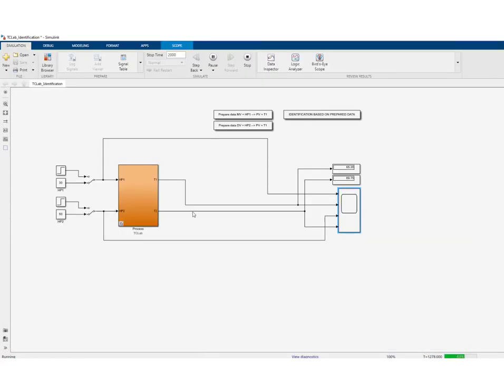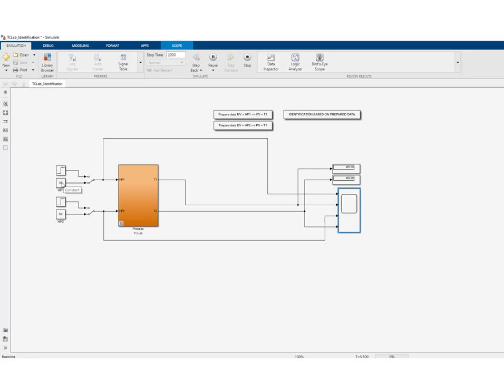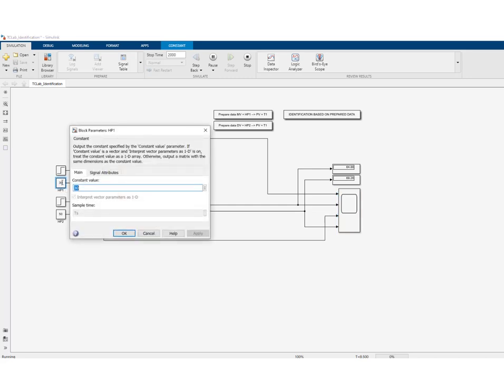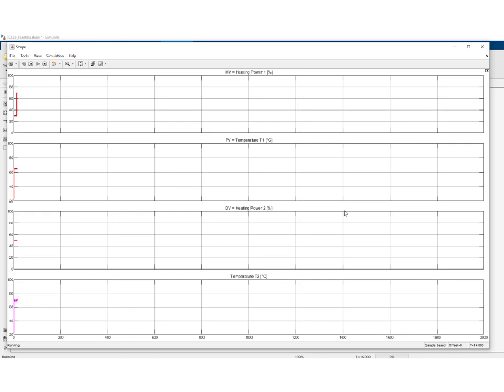What we'll do now is stop the simulation very briefly and restart it — since this is very short, it will have no effect. We then perform our step change. This is the experiment we'll use for identification: we have increased MV from 30% to 70%, and we observe the influence on PV, the first temperature.